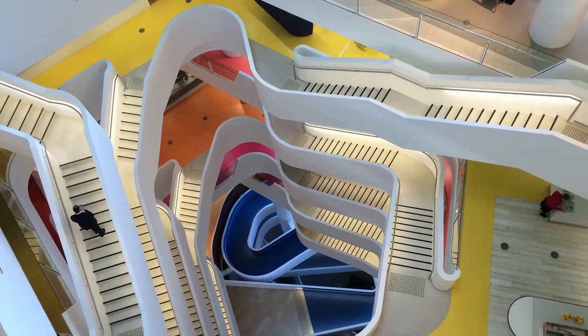The second is the airflow distribution. Usually for a building not purposefully designed for this, we can only use the stair and lift core as the air distribution path. Most of the time we would try to avoid using the lift core because we need to provide safety barricading of the open lift door throughout the entire process, which most builders would try to avoid as a risk. And if the building doesn't have a large atrium, that restricts the airflow between different floors and the even distribution, which makes the process a lot harder. Last but not least is all the mechanical systems, and how easily they can be isolated from the ambient. Usually that's part of the damper, but for a lot of the older buildings, the fresh air dampers have a certain minimum fresh air requirement and can't be shut fully.